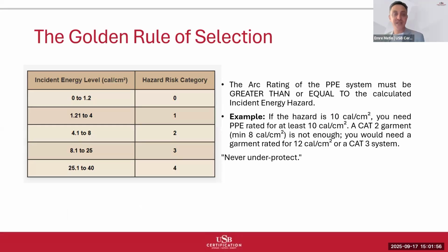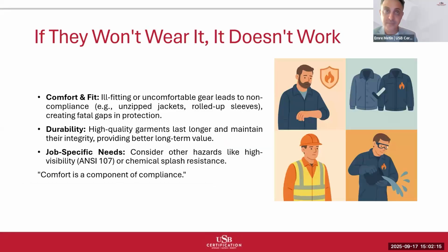The golden rule of the selections. Here is the fundamental principle that governs all arc flash PPE selection decisions. The arc rating of your PPE system must be greater than or equal to the calculated incident energy hazard. Never underprotect.